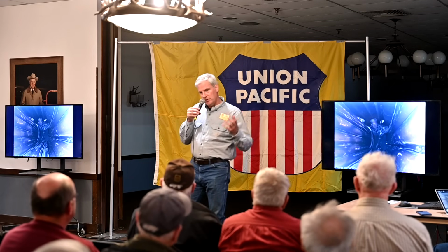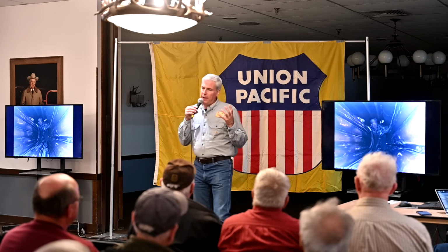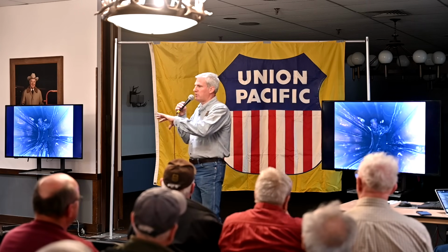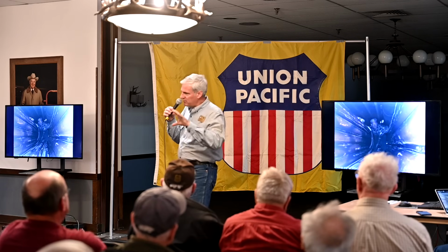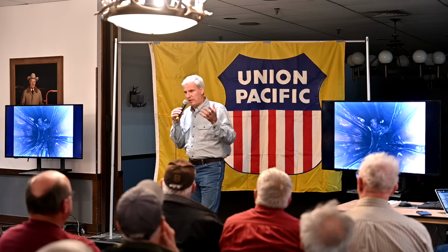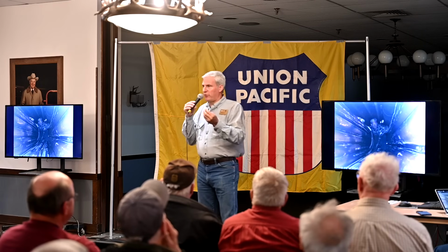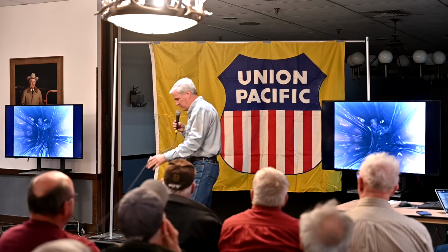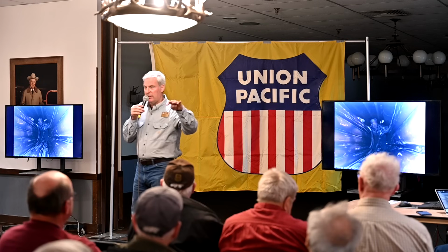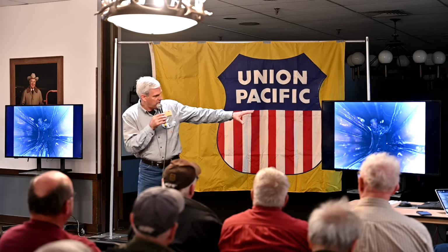So here we are. We're evaporating 200 gallons of water a minute. Well, in that water is all of the stuff I've been talking about. Now we've got some chemicals in there to help us manage it. Those chemicals will react with some of the bad stuff in there and prevent it from sticking to the metal. We've got another really cool chemical reaction, diethylhydroxylamine. What that does, it reacts with free oxygen. And by the time it's done, through this really cool looking chemical calculation, it's acetic acid, which is a weak vinegar. So that takes care of the oxygen, so the oxygen won't hurt the metal.